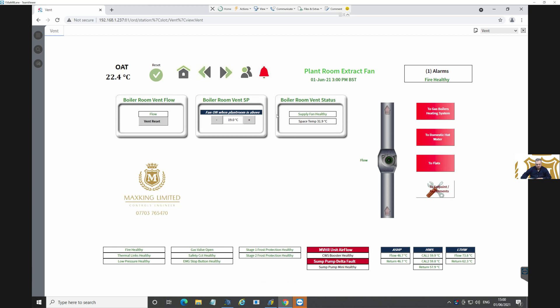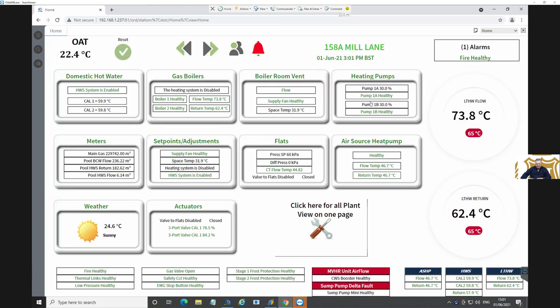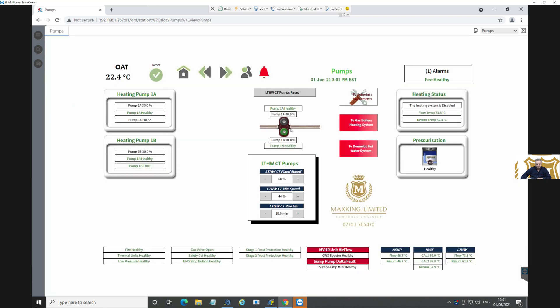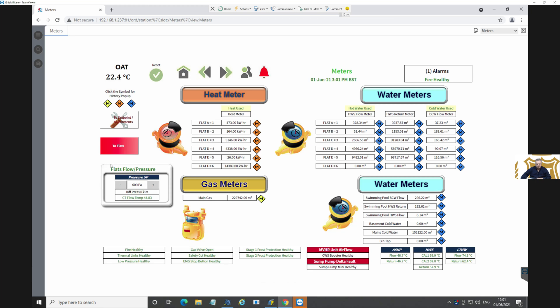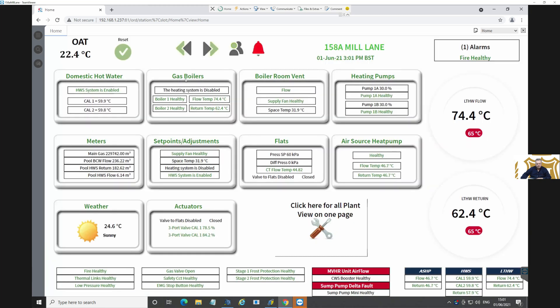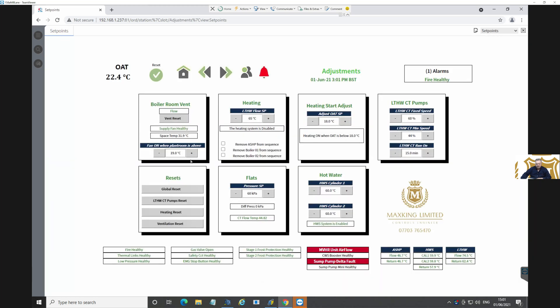Boiler room vent - finds out when the plant room is above 19 degrees. Space temperature is 31.9, so it's quite warm in that plant room. Heating pumps - can't see anything wrong there. Nothing wrong with the meters, they all look good. If there was a point that was stale it would have a different background. If the background's okay, then I know it's reading the information.